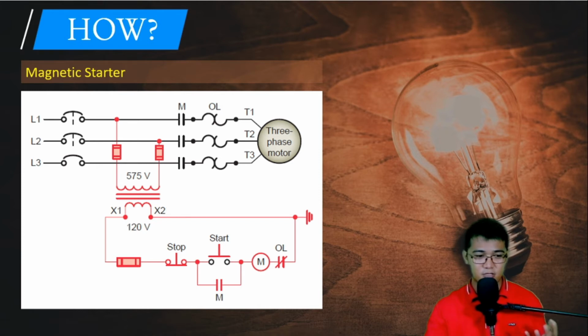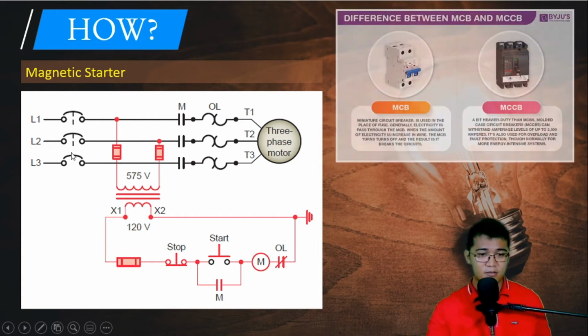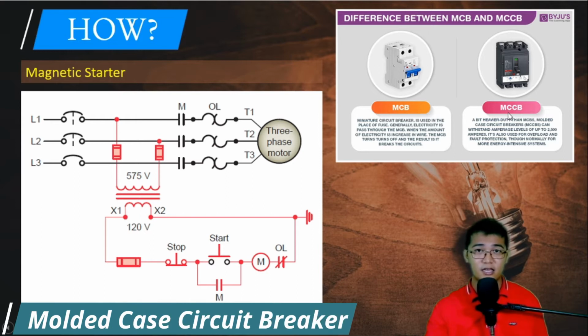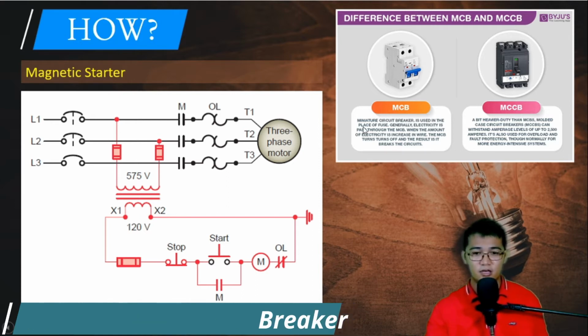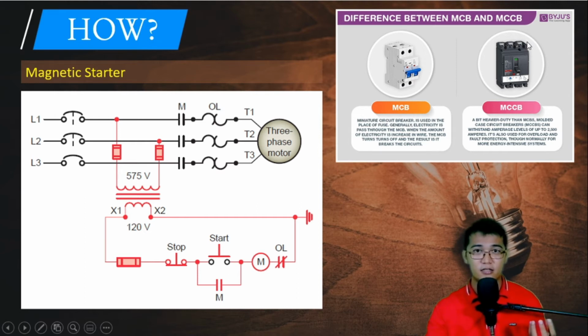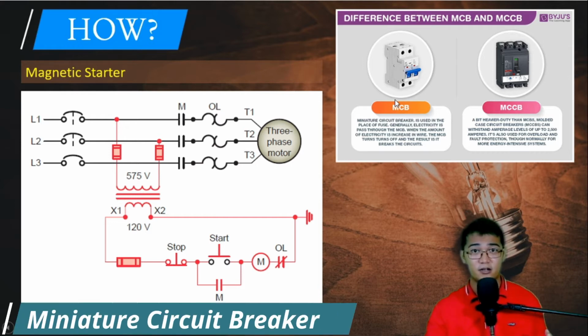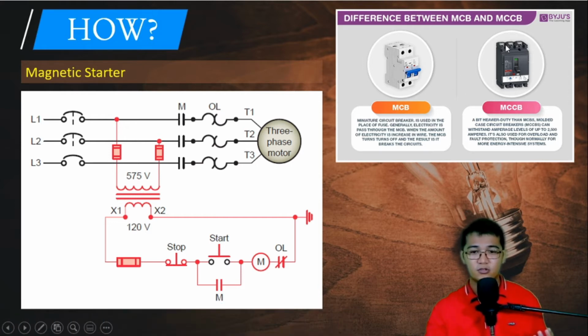Let's observe. So here we have this particular symbol. We have the line voltages, line 1, line 2, line 3, same as the manual starter. We have this symbol, which is actually the MCCB, or molded case circuit breaker. This type of breaker is solely intended for high power applications. It can withstand amperage levels of up to 2,500 amperes, so it's more heavy duty compared to the MCB, or the miniature circuit breaker. So for motors, this is what we use, the MCCB, molded case circuit breaker.